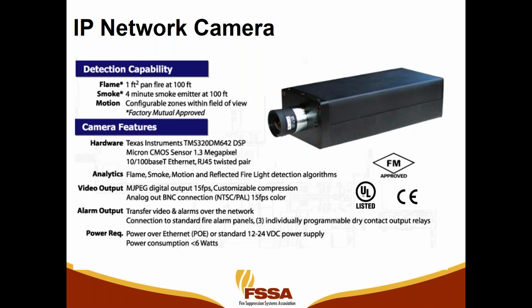Relay 1 can be smoke or flame or any algorithm. Relay 2 is trouble. And then relay 3 can be a separate algorithm from relay 1. So say smoke on 1, flame on 3, so that you can differentiate at the panel whether it's a smoke or a flame alarm. Now, video analytics cameras are a listed NFPA initiating compliant device, so they can be connected to a releasing panel.